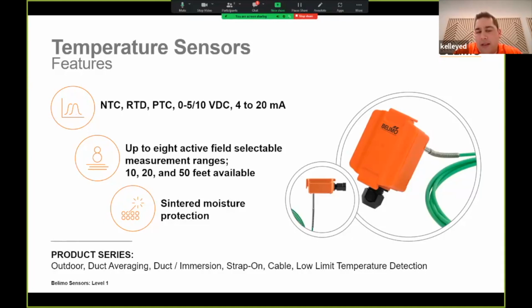You see that middle line, field selectable measuring ranges. So what this means is one part number, you could potentially install in 8 different types of zones in one facility. So I could say we have our temperature sensors here in the conference room. We use the exact same temperature sensors down in our kitchen in the freezer area. They just switch the measuring range over, of course, specifically for that zone. So again, ease of installation in our world is also tantamount to part number selection, you know, especially for stocking backups and spares and so on.